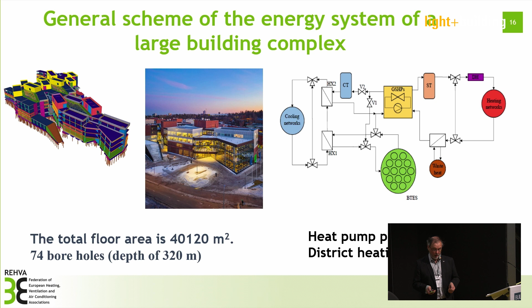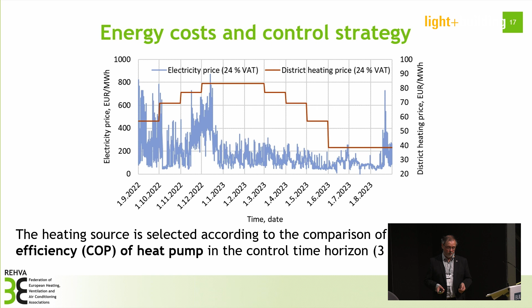The idea here is to analyze how we can optimize the use of the system, where we have two energy systems: a ground source heat pump and district heating. In this case, district heating is based on seasonal pricing, and the price signal is analyzed over a 3-hour time horizon. This means the system can be controlled in 3-hour periods, not hourly, because it's not practical to just switch heat pumps on and off - they need time to react.